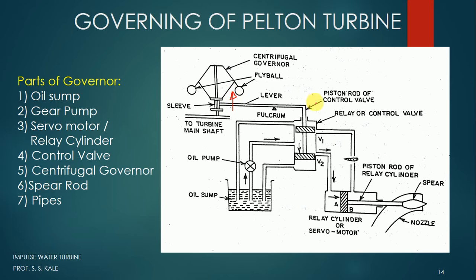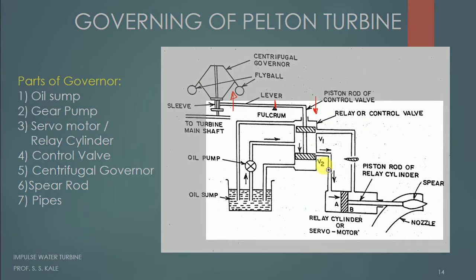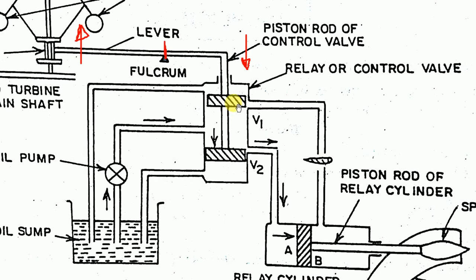As the lever moves up on the governor side, the other side moves down due to the fulcrum. When that side moves down, the two pistons of the control valve also move in the downward direction. In the current neutral position, both valves V1 and V2 are closed. When the pistons move down, the oil coming from the pump now flows to valve V2.